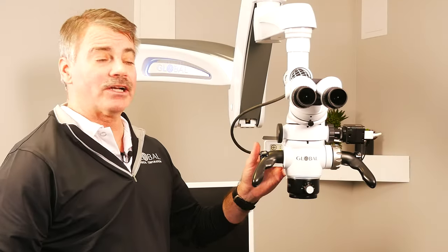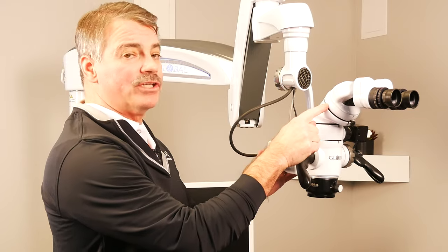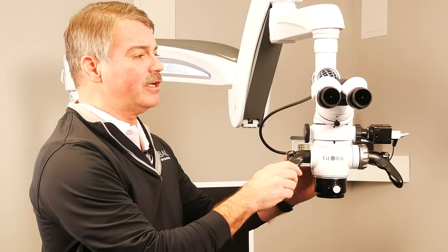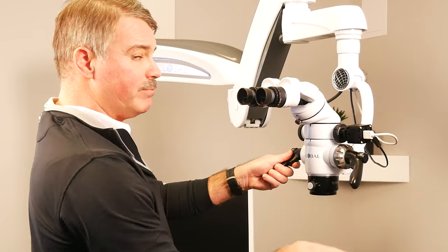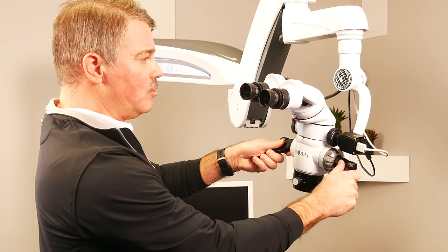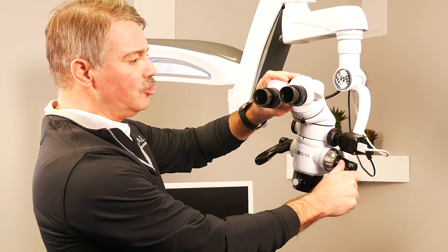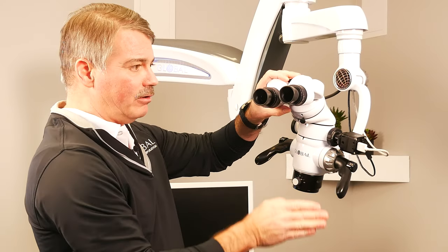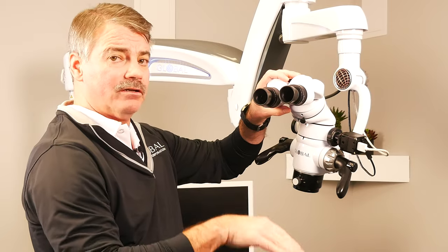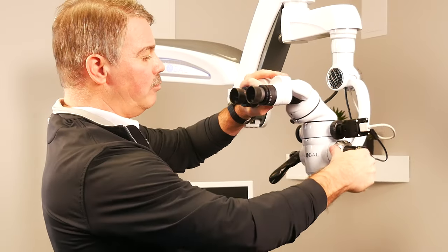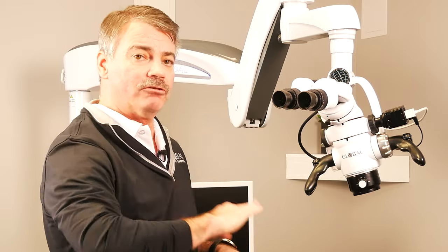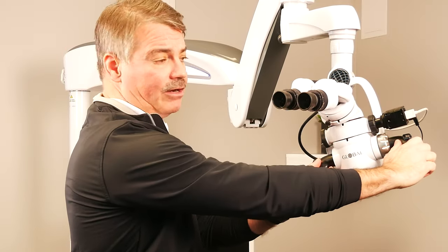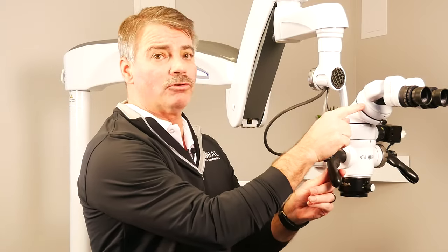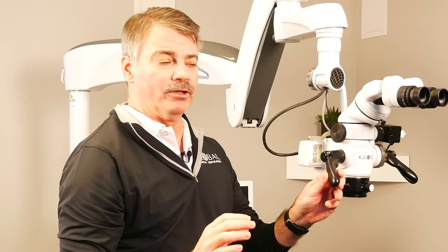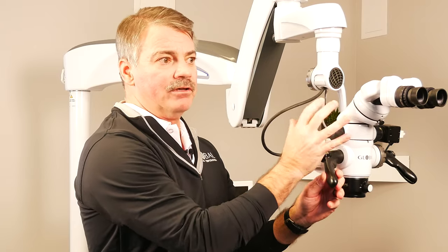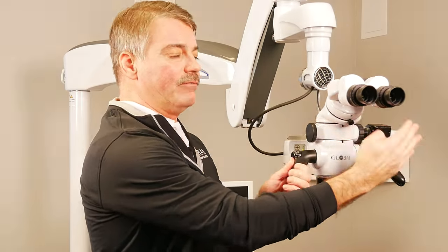Right on top of the car extender is what we call our binocular rotation ring. This allows for a doctor who has to work off axis, say tip the microscope to one side, to simply turn the binoculars so they're still parallel to the floor, allowing the doctor to sit in an upright ergonomic position. It'll rotate left or right, a 15-degree swing on the positioning of the microscope. One important note is the binocular rotation ring only functions properly if it's attached to a car extender. They work in unison to provide that efficient movement.